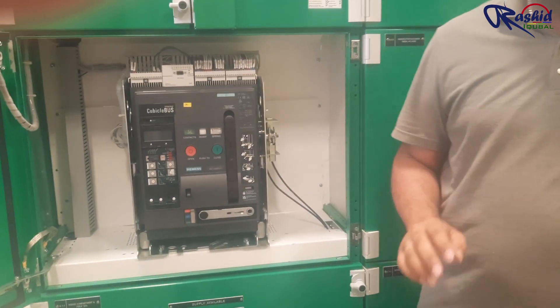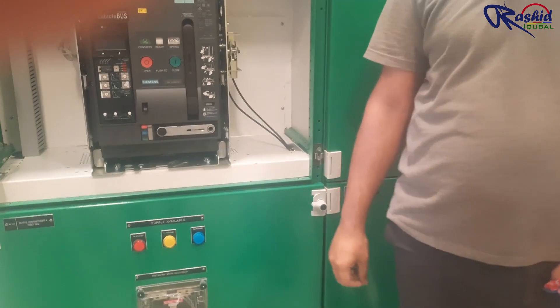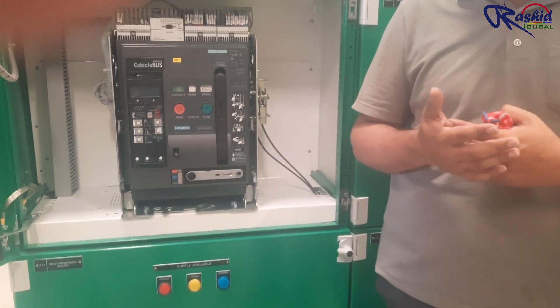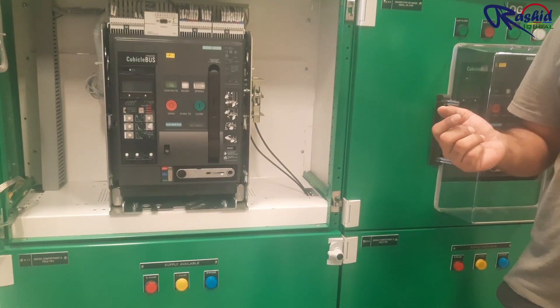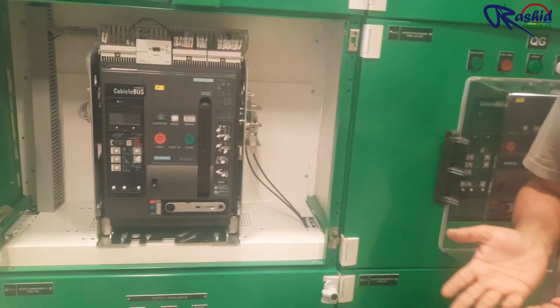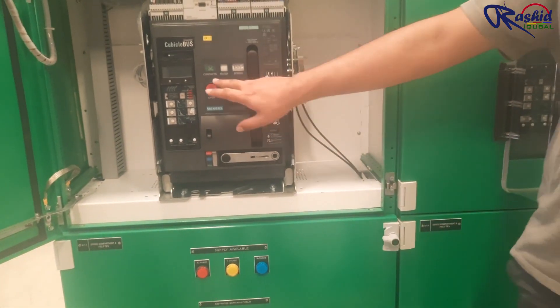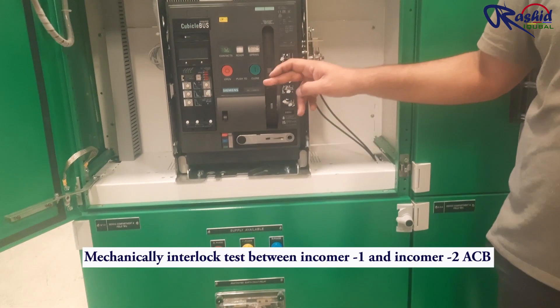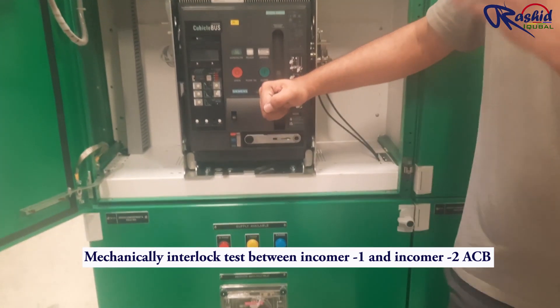Now this mechanism is fully connected. There is a motorized mechanism — whenever you need any operation, the motor will charge the ACB automatically. But if your motor power supply is not available and you want to manually check whether it is working, you can operate the ACB mechanically. For this, you first have to charge the spring — this lever has to be brought down nine times.